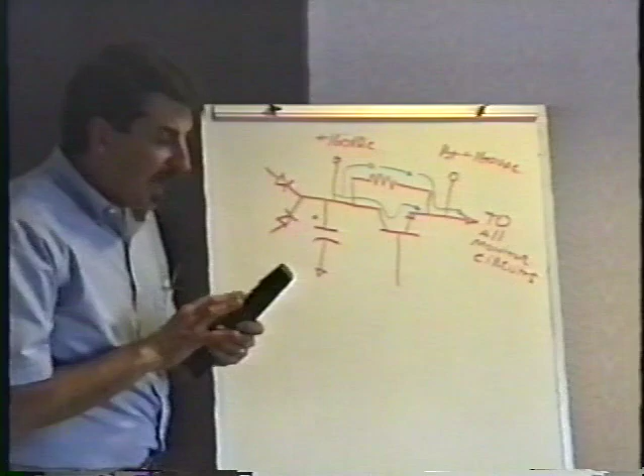This can be rather confusing because you get to the monitor and it appears completely dead. And yet you check the power supply voltage and you've got tons of voltage there. You've got even more than you expect. So that's confusing thing number one, because you're getting to the monitor, it's completely dead, and you're thinking, well, I don't know, is the power supply bad? How come I don't have anything? The monitor doesn't make any noise, it doesn't do anything. But you check the power supply voltage, and you've got way more voltage than you need. What the hell's going on here? Okay, everybody with me so far?